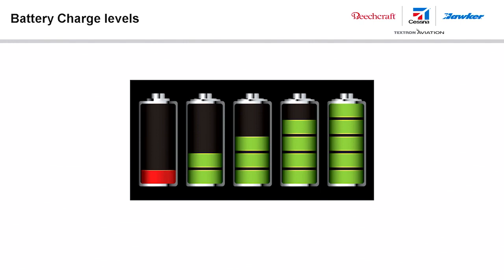A battery fully charged to 28.5 volts will self-discharge to 27 volts in about 90 minutes, at which point the electronics enter low power mode. In low power mode, the electronics will self-discharge the battery in about 6 months. When self-discharged to a voltage that is too low, the battery can be permanently damaged and may not be dispatchable. The battery should be boost-charged regularly to avoid damage.